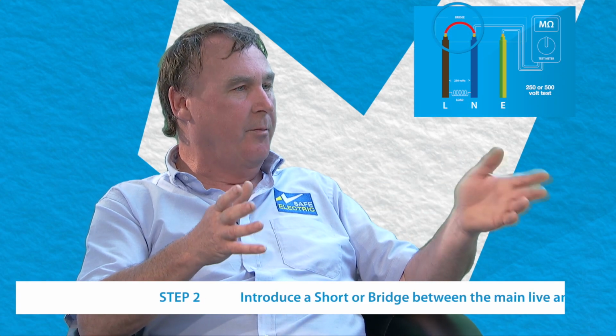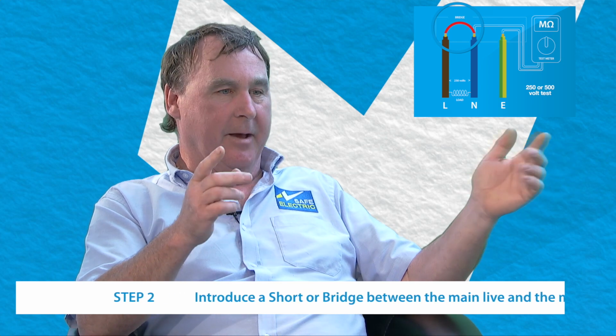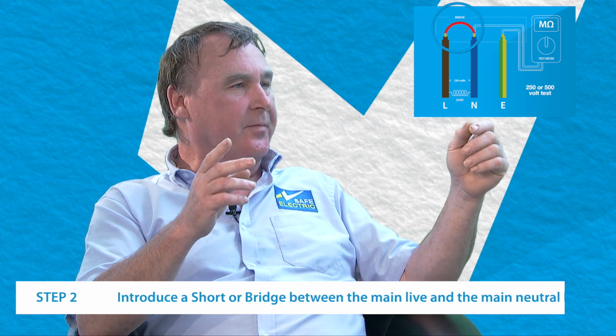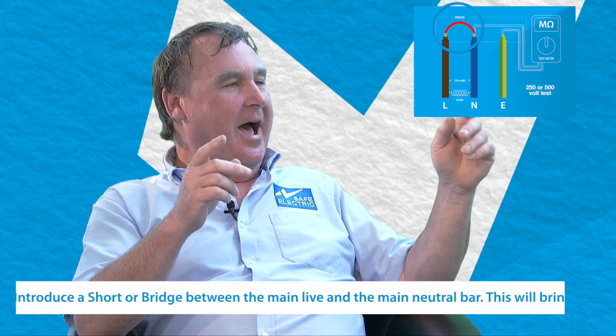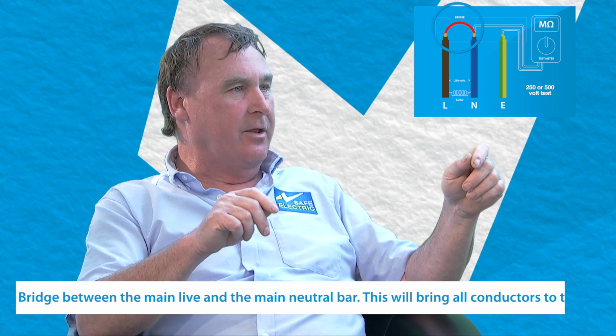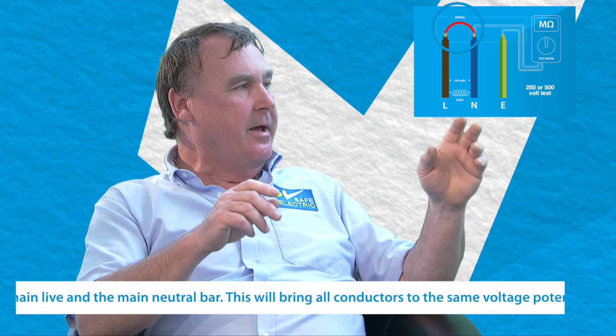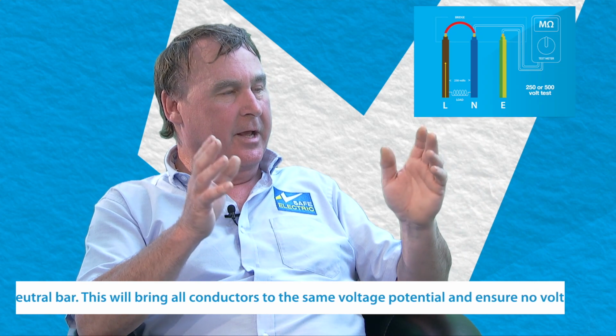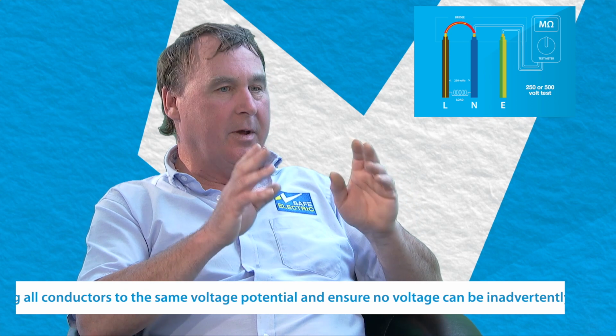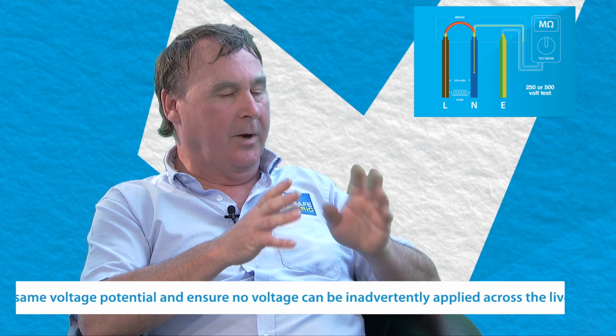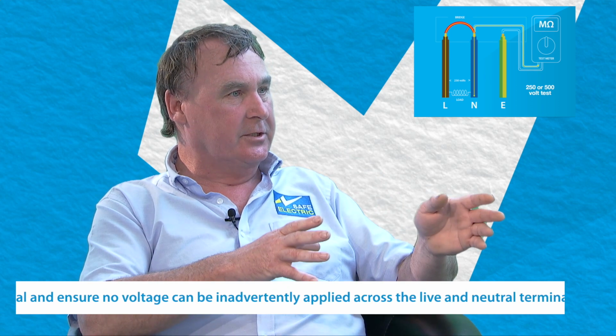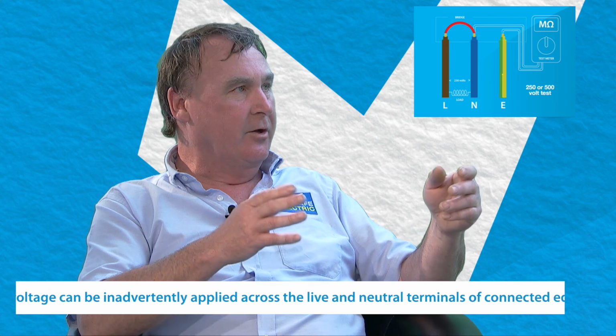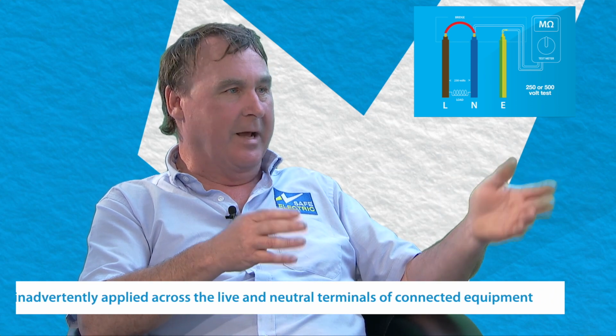You have now disabled the neutralizing link, which should be the only place in the electrical installation where neutrals and earths are connected together. Step number two, get a piece of cable, 1.5 or 2.5, about 20 centimeters long, millimeters would be a bit short, and short out your main live to your main neutral. This, of course, is a power-off test. That's a very important step, because now you're bringing all the conductors in the installation to the same potential, and it is now impossible to apply any voltage which your test meter might generate across the loads. You don't have to take out any bulbs. You don't really have to plug anything out if you use this method.